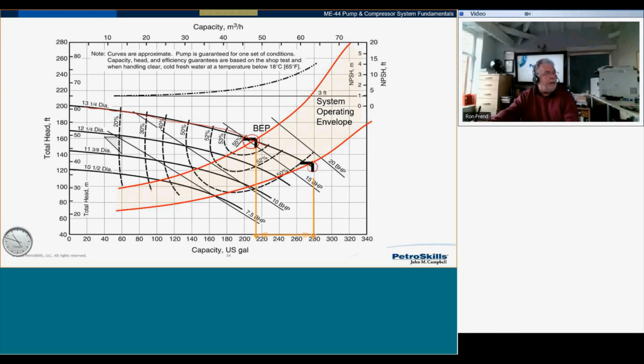Notice that the flows are now substantially different. If we go up to the NPSH curve, what we find at BEP flow, we've got about 2 meters of head, NPSH, which isn't too bad. But if we go to the high flow, our NPSH, which is now NPSH required, has gone up to 4 meters. This now starts to get a little bit scary. You've also got a change in power requirement. There's all sorts of stuff going on.